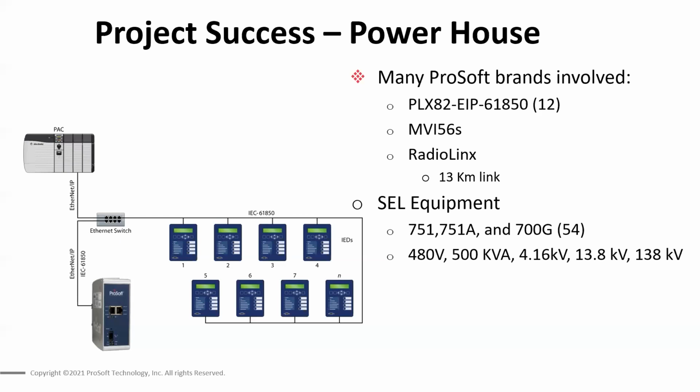We've had some issues with the gateway module where it did not like when devices disappeared from the network. This caused the driver to fail and try to recover, and the data from the IEDs was stale. Can you speak to improvement for the in-chassis module? Yes, we have done some enhancements to some of the error handling on the new in-chassis module.